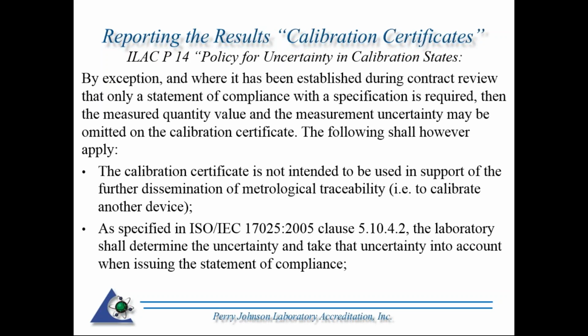Hence, during the contract review process, it needs to be determined whether or not these devices are going to be used to calibrate other devices. So I hope that's clear there. If it is, then reporting a statement of compliance on an accredited report will not be acceptable.